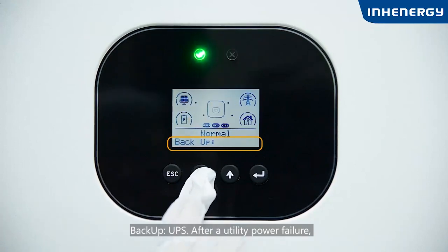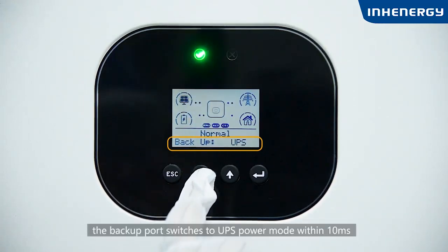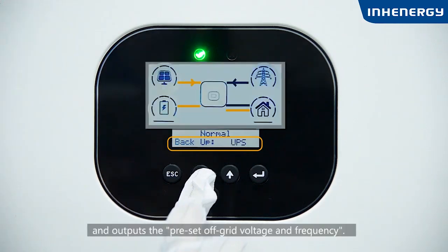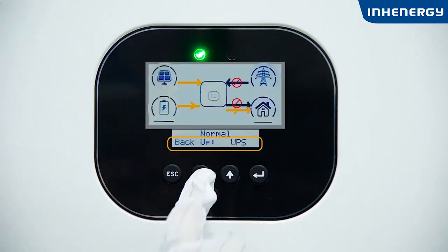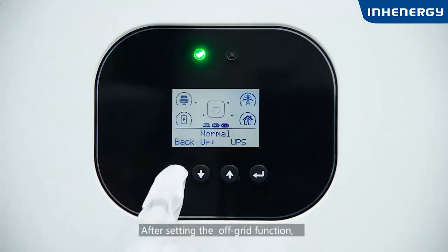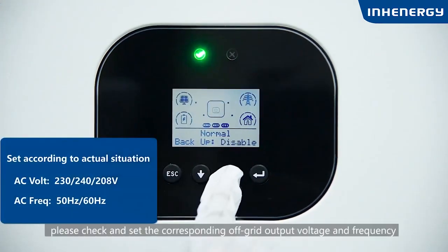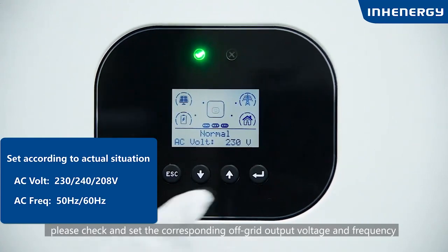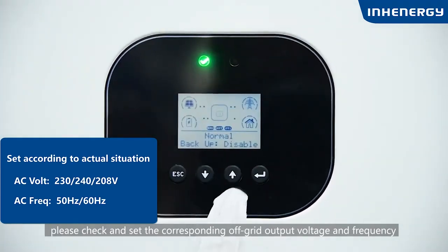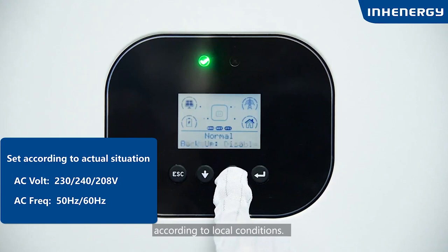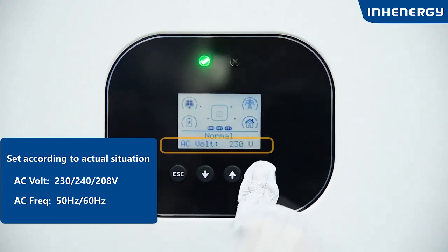Backup UPS: after a utility power failure, the backup port switches to UPS power mode within 10 milliseconds and outputs the preset off-grid voltage and frequency. After setting the off-grid function, please check and set the corresponding off-grid output voltage and frequency according to local conditions.